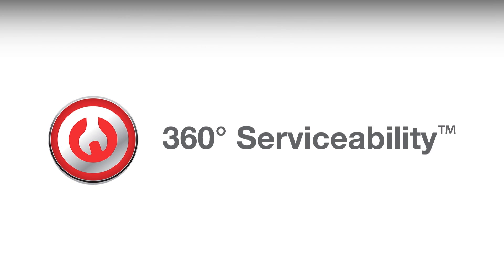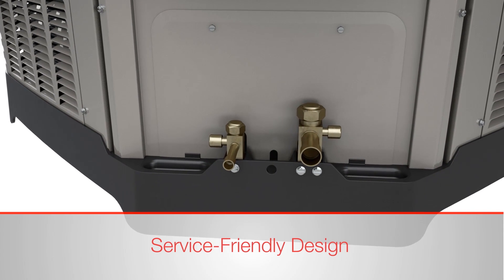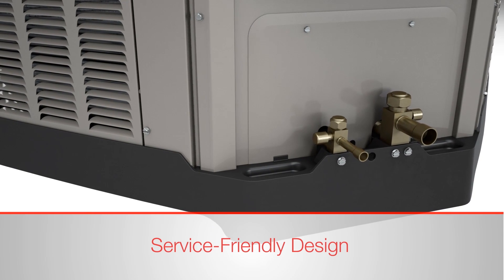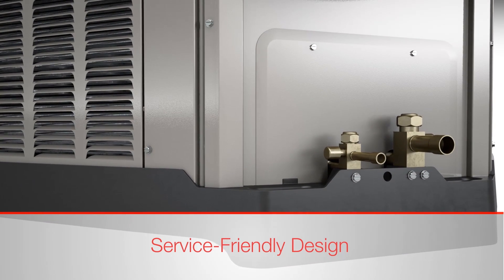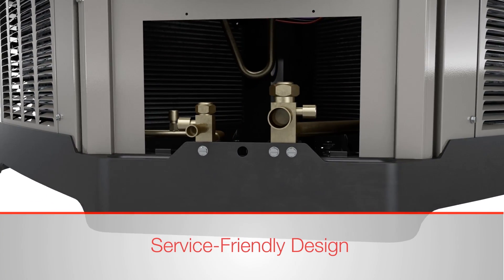360 serviceability equips Ruud dealers with features that speed up service calls. This service-friendly design includes easy access to external gauge ports, which makes hooking up gauges and servicing simple and fast. The design also includes a unique service window that allows access to high and low-pressure switches, as well as heat pump TXV and reversing valves to perform diagnostics while the unit is running.